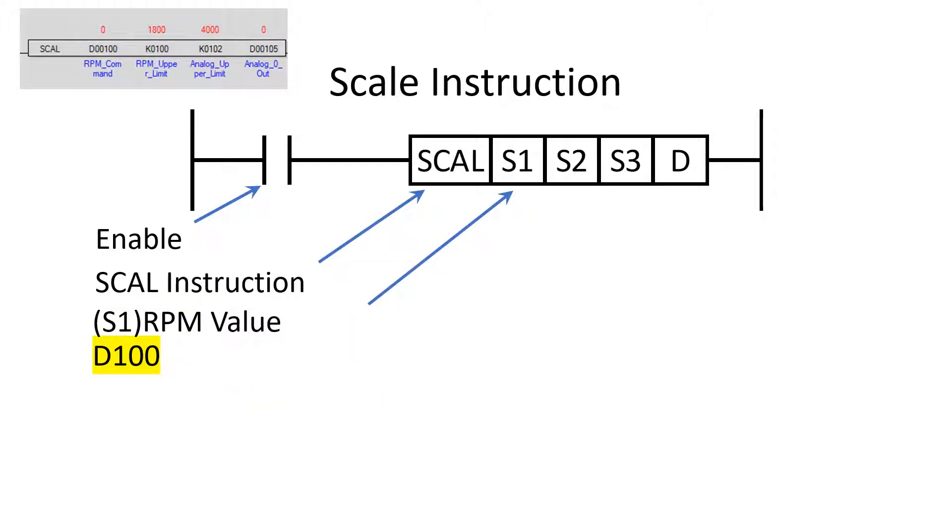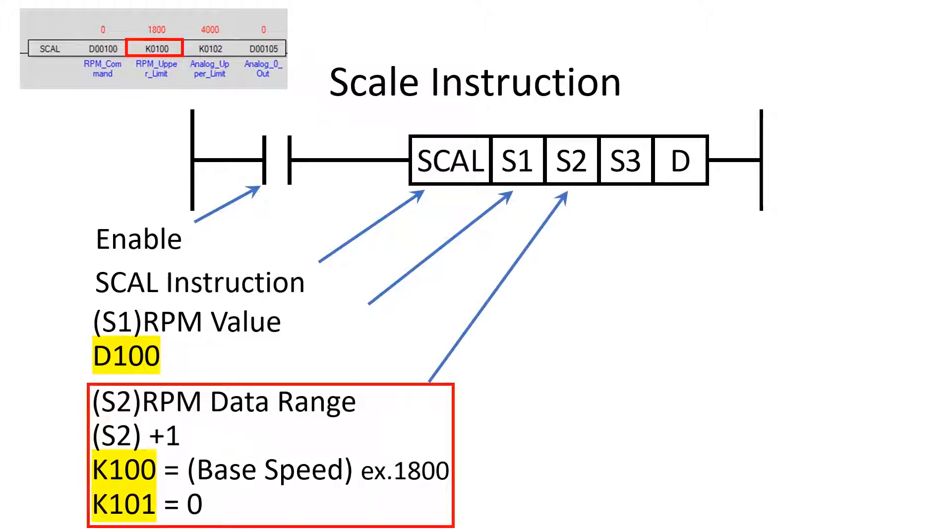Operands S2 and S3 are stored in K memory as this is retentive memory. The S2 operand is the memory location of the motor's base speed. In this example it is 1800. S2 plus 1 is the memory location for the lower value of the motor's base speed. The two S2 locations are K100 and K101 for a range of 0 to 1800.